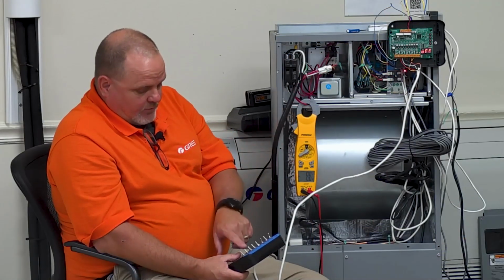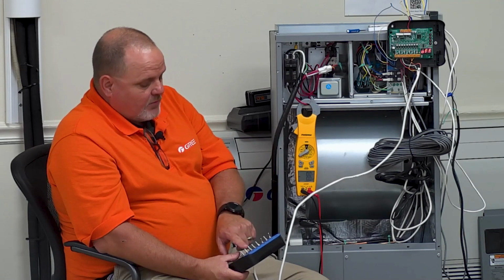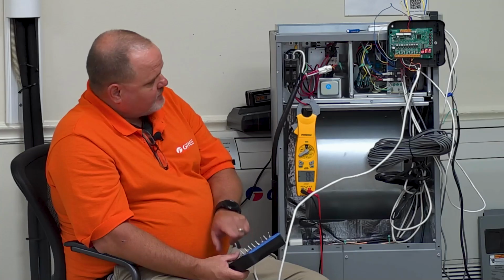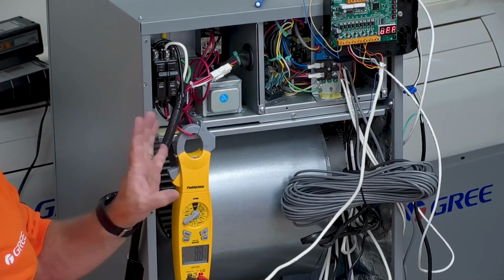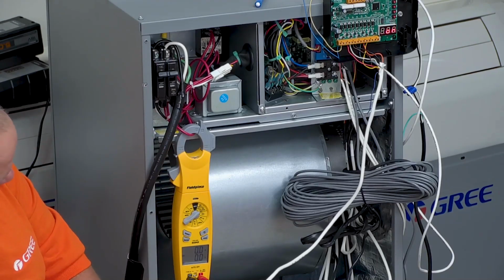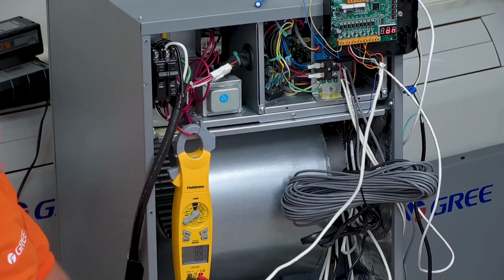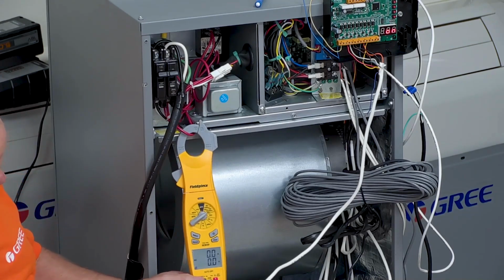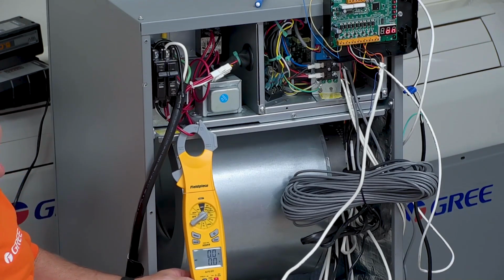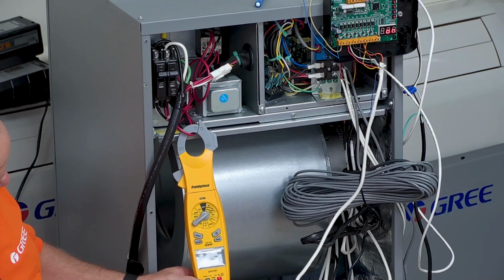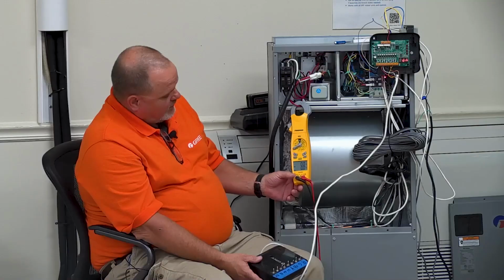And the heat pump shut off, thank God, because I didn't want that on very long. All right, so now let me give it an emergency heat call. As I told you before, I don't have to have a fan call. I can just give it an emergency heat call. It went to on, blower's coming on, and in a minute here you will see the amp probe show that the electric heat's on.